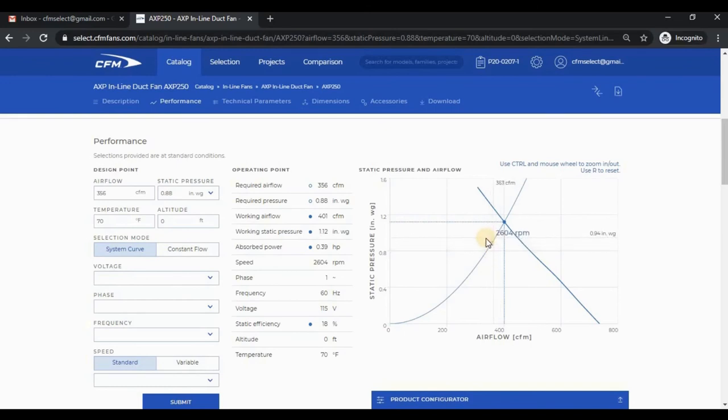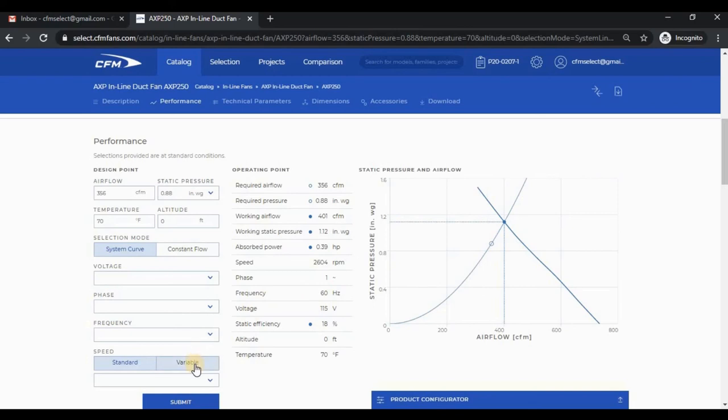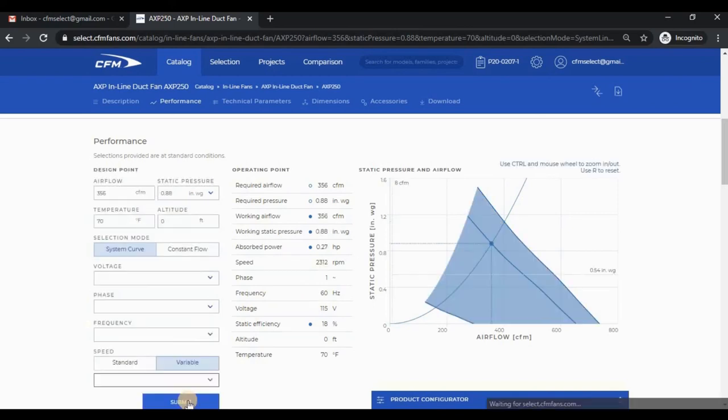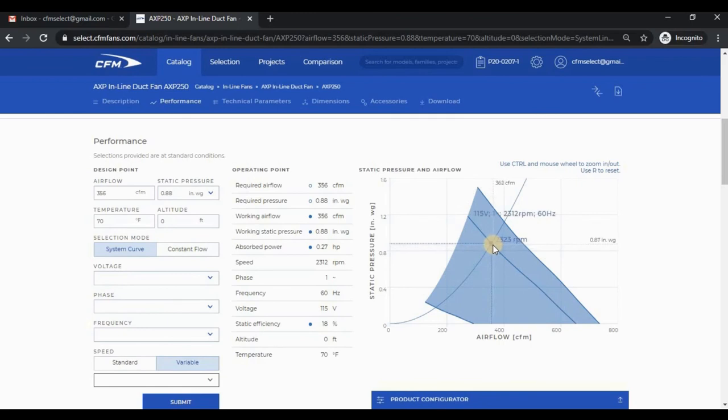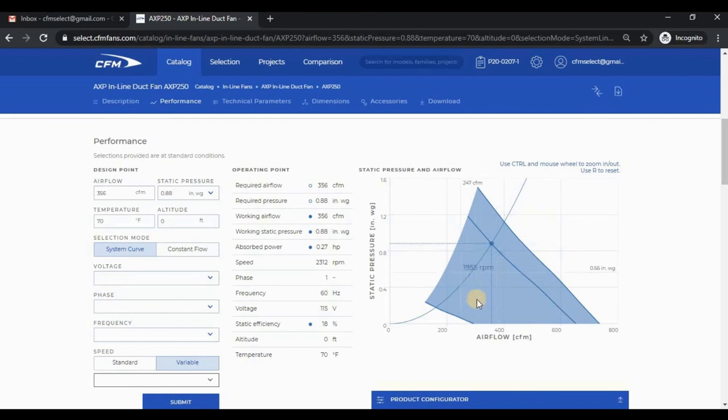I can change the speed selection to variable and click submit. You can now see that the fan was slowed down to intersect the design point. The shaded region is the acceptable range for speed control.